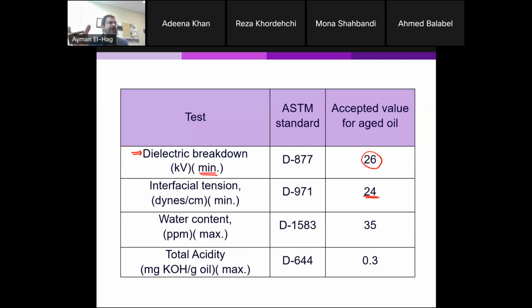Now, why are we talking about aged oil? Because we are talking here about field tests, so those are the typical values you will find in the field. For the water content, the maximum value is 35 parts per million. For the acidity, the maximum allowed value is 0.3. What if it exceeds these limits? What is the action here?